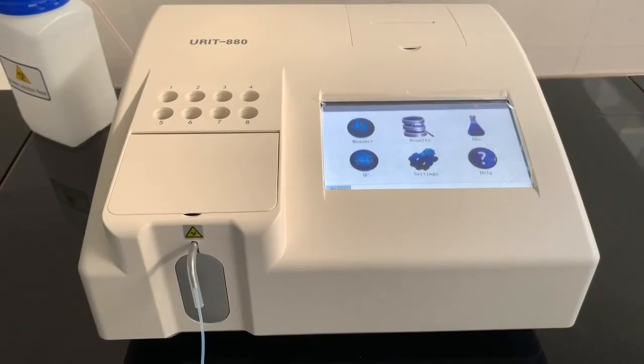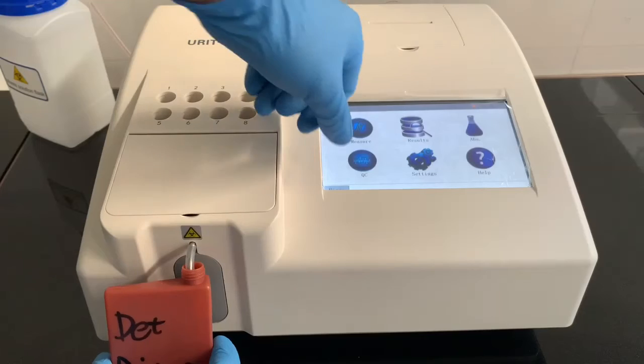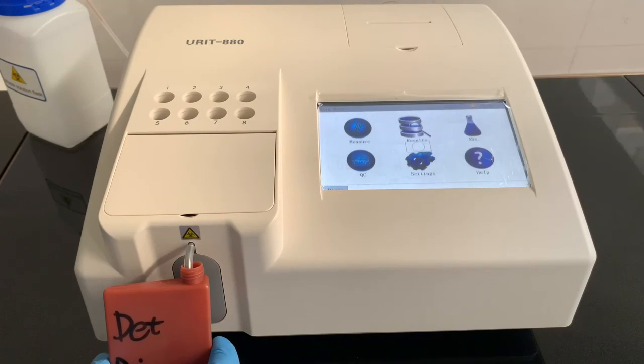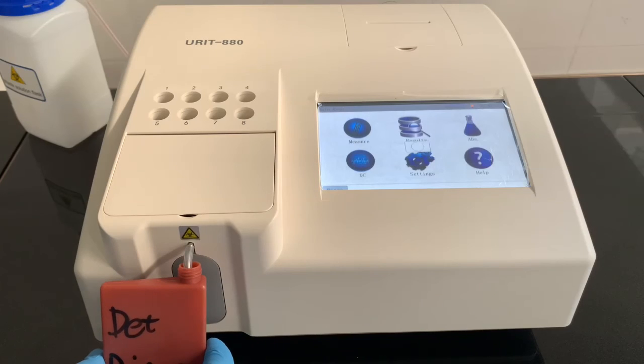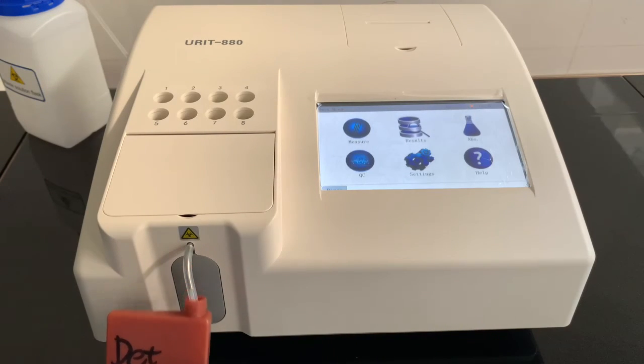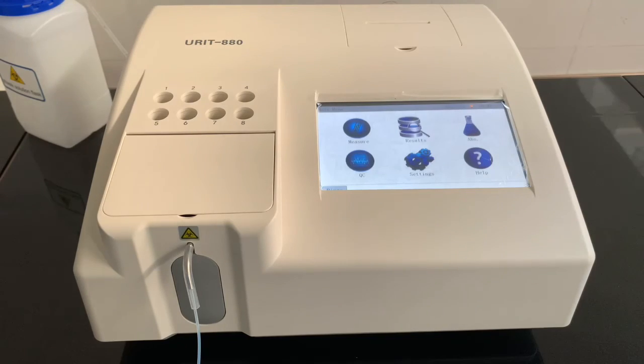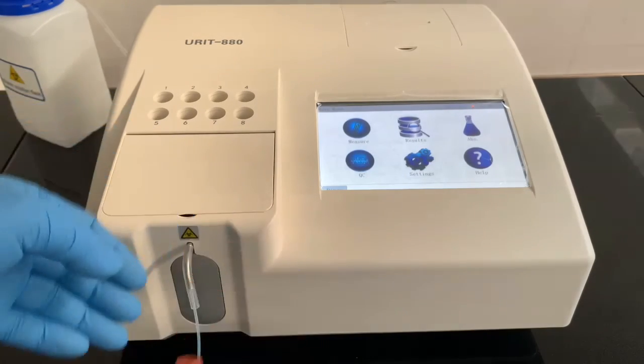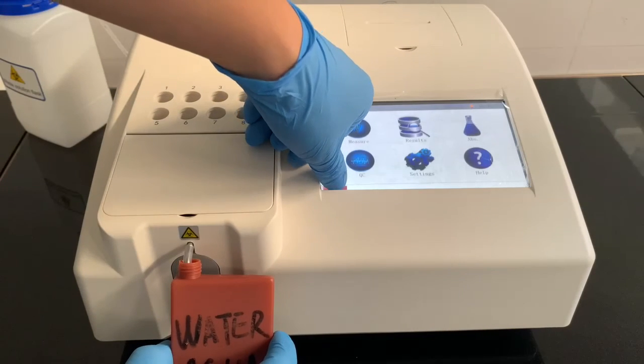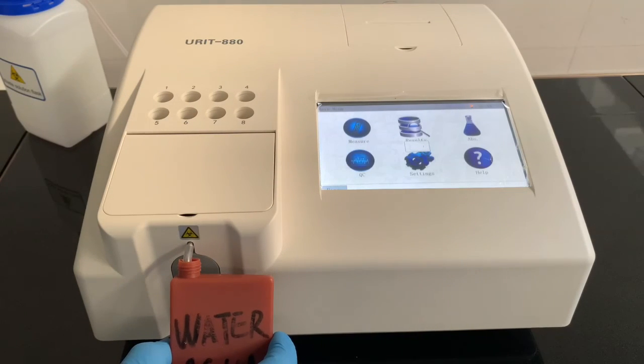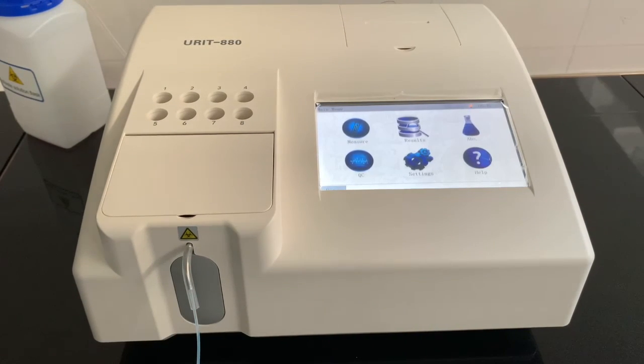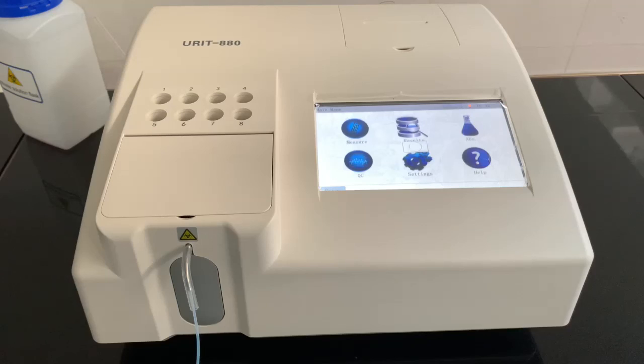Before we shut down, we have to rinse with detergent first. Tap the rinse. And then we rinse again using water. Also tap the rinse. And at last, we tap the rinse again to remove all the liquid outside the analyzer tubing system. Now we can switch off analyzer directly.